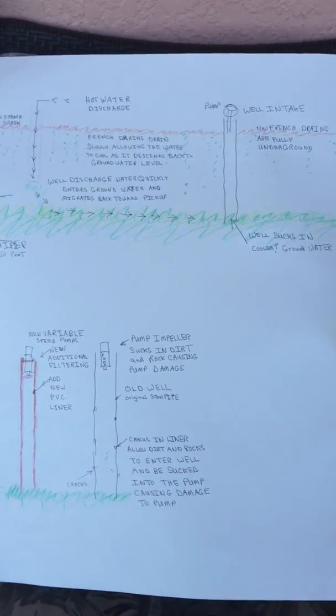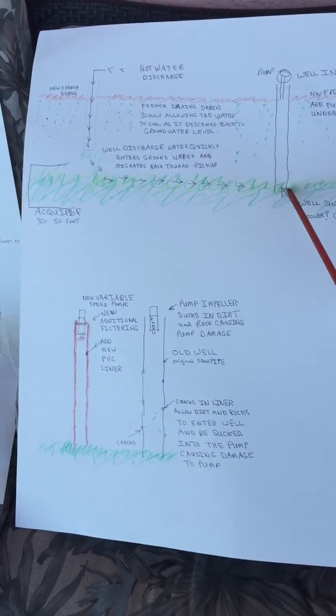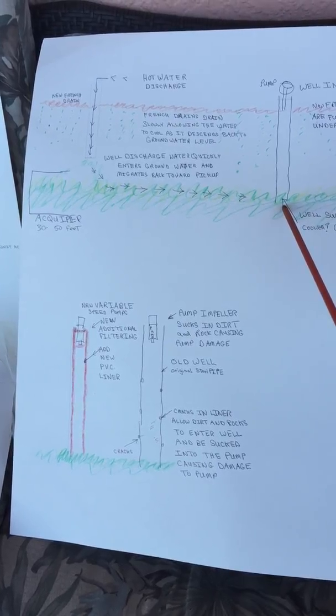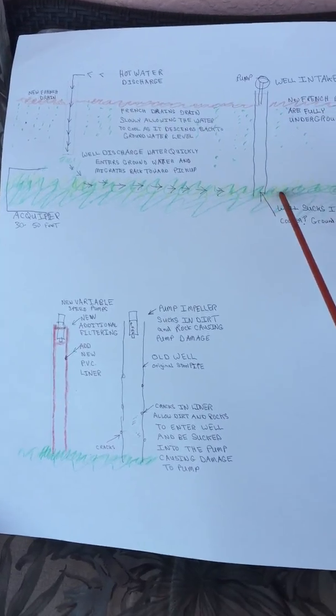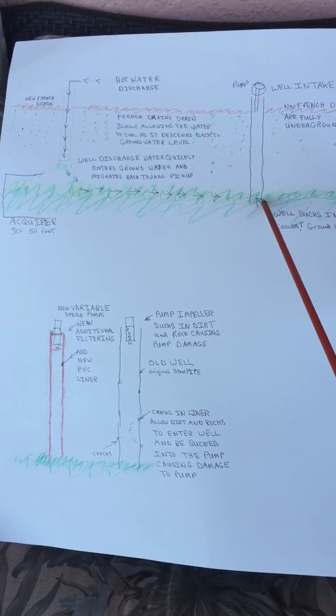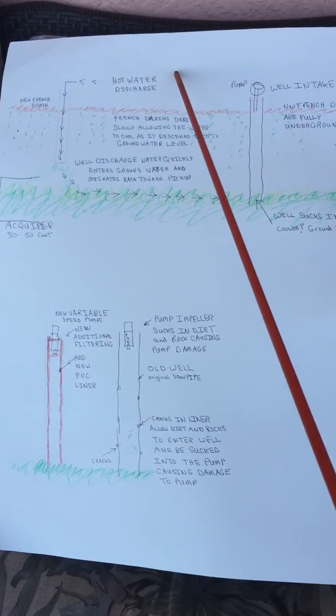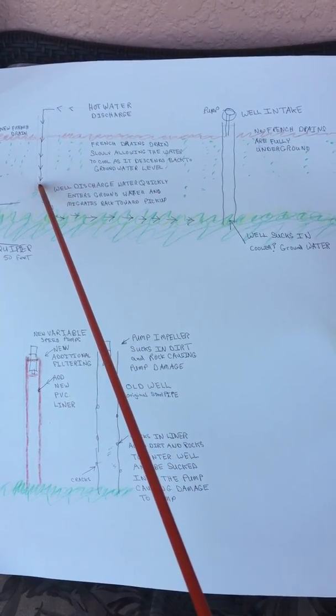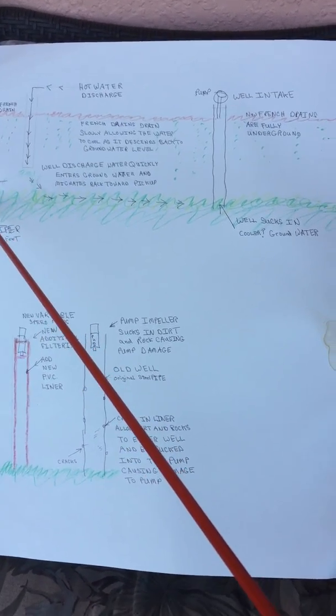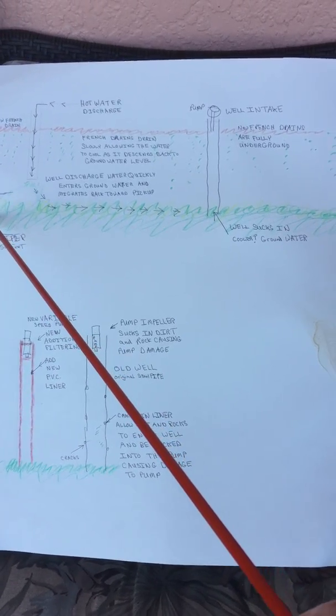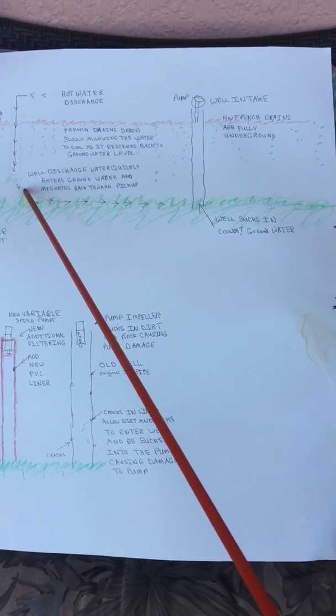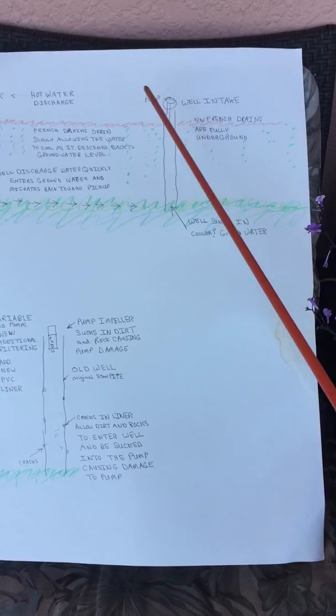The other problem is the wells pull the water in from the aquifer, and this water is warm. One of the reasons it's warm is because when we discharge the water after we go through the building, the discharge well, the aquifer underneath our building is only about 30 to 40 to 50 feet deep or wide. So this hot water coming back, our own hot water, goes back in and migrates over, and it's sucked up by the pump and repeats the cycle and never really gets cold.